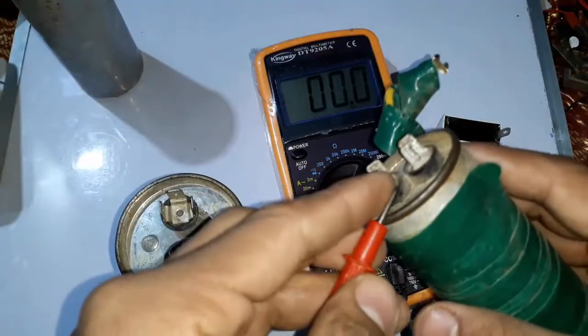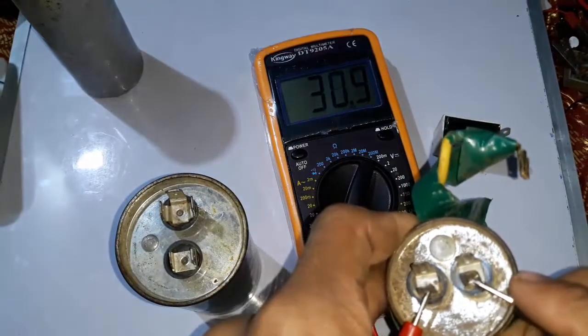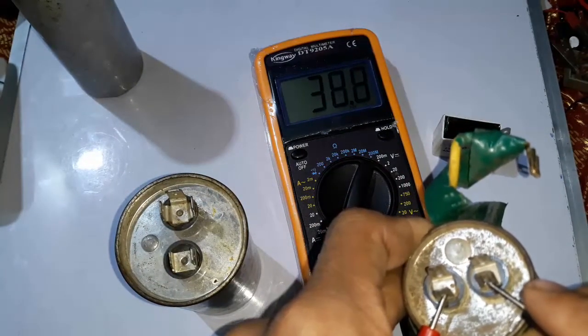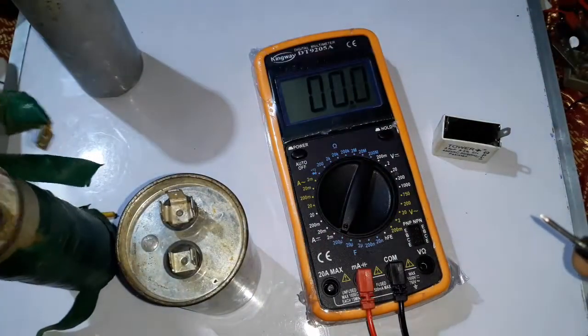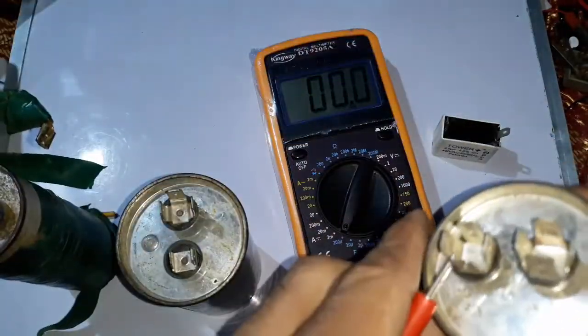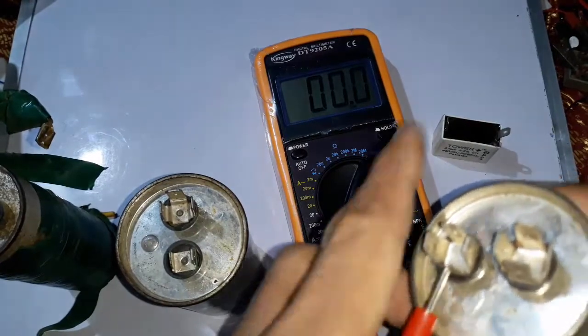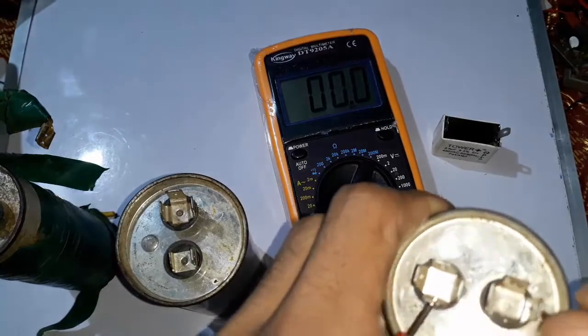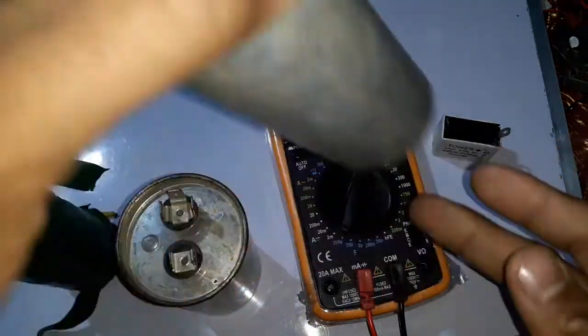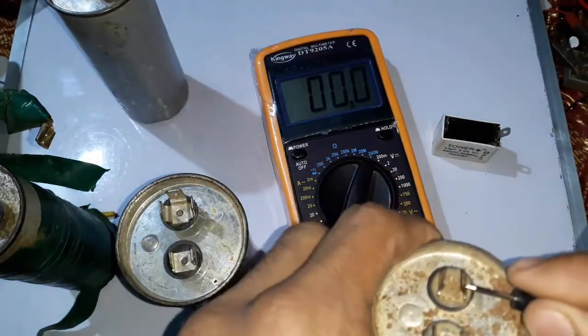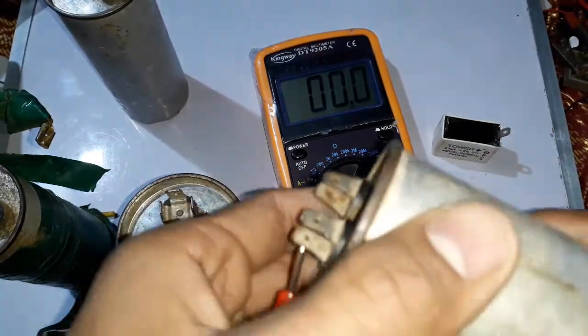The next capacitor is 38.8 microfarad and the next one doesn't show any value, which means this capacitor is dead. Here is another capacitor and this capacitor is also dead.